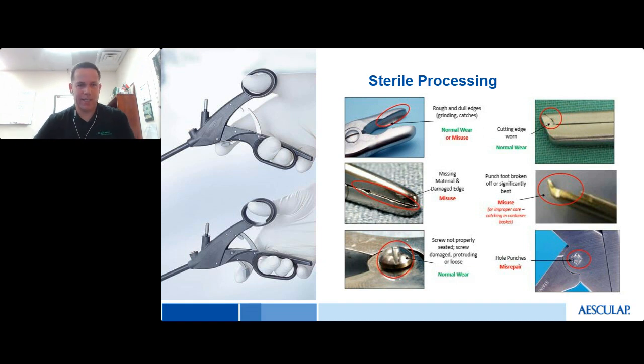If we look at some examples I've prepared here, we have the rongeur on the very top, very common - we're going to have some wear and tear to the working end. The cutting edge may not be as nice and smooth as it should be, therefore the function of this device could be compromised. This could also potentially come from misuse. Not to pick on the surgeon, but we've seen so many examples over the years where the instrument is used for something it's not intended to be used for, and this could also be an issue.